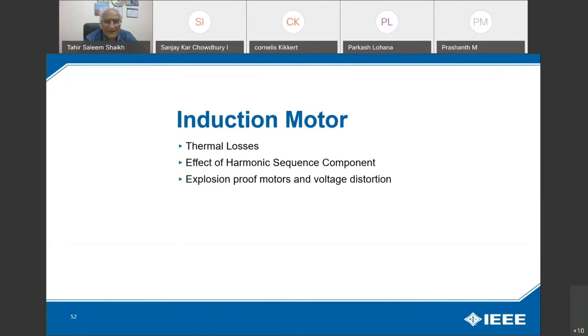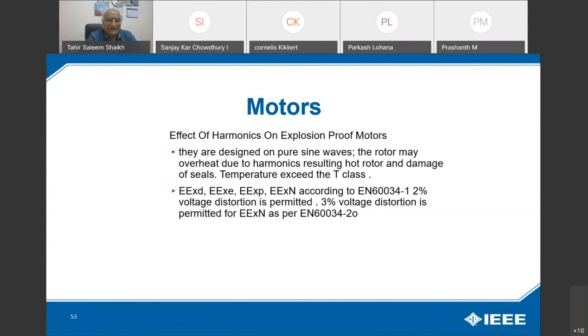Induction motor, again, in this the thermal losses will increase, with effects of harmonic sequence components, and voltage distortion. Take an explosion proof motor of a certain temperature classification, T1 to T6 being the classifications for hazardous areas. If you use this in such an environment where the temperature rises, this will destroy the seals of the motor, the temperature classification will change, and it will no longer be a hazardous area motor. So you can see, explosion proof motors are designed on a pure sine basis. The rotor may overheat due to harmonics, resulting in a hot rotor and damage of seals, and the temperature exceeds the T class.